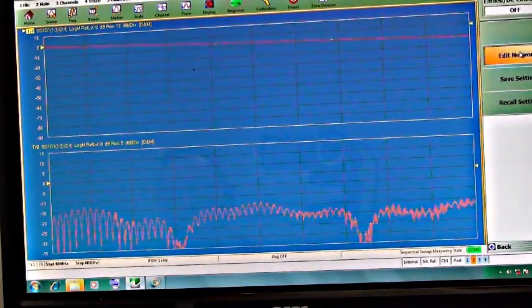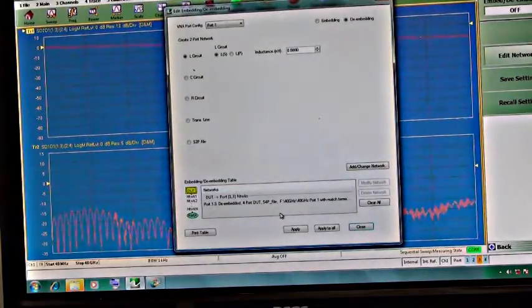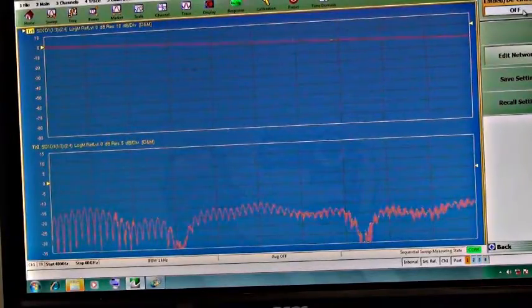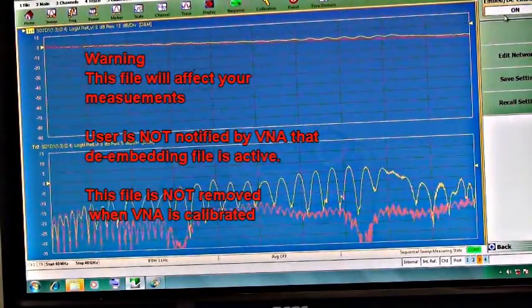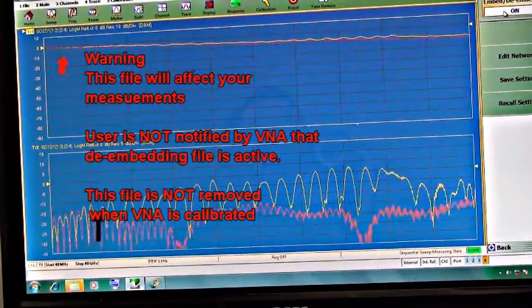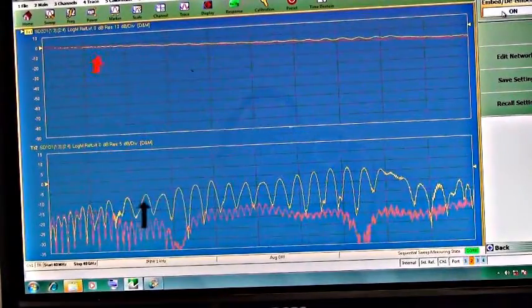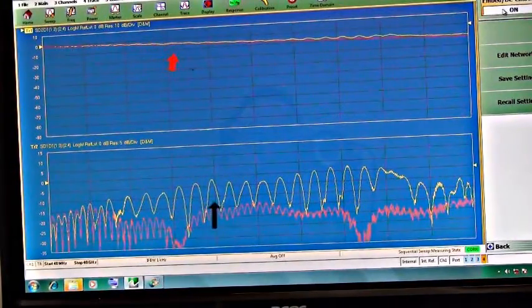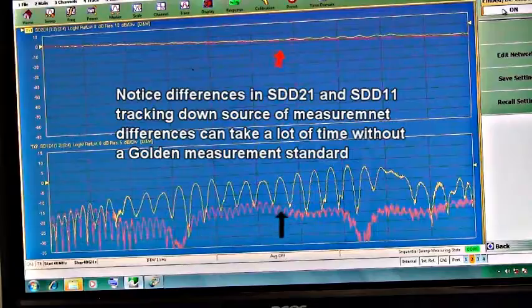We have a network that we have pulled in from a USB drive, and we're going to apply that now to the measurement. So now there's a structure in there that says it's being de-embedded, but it's really not. So I can verify the fact that this board is not performing the same. So now I know again, well, I either have a setup problem or I have a bad calibration. I need to go back and recal.